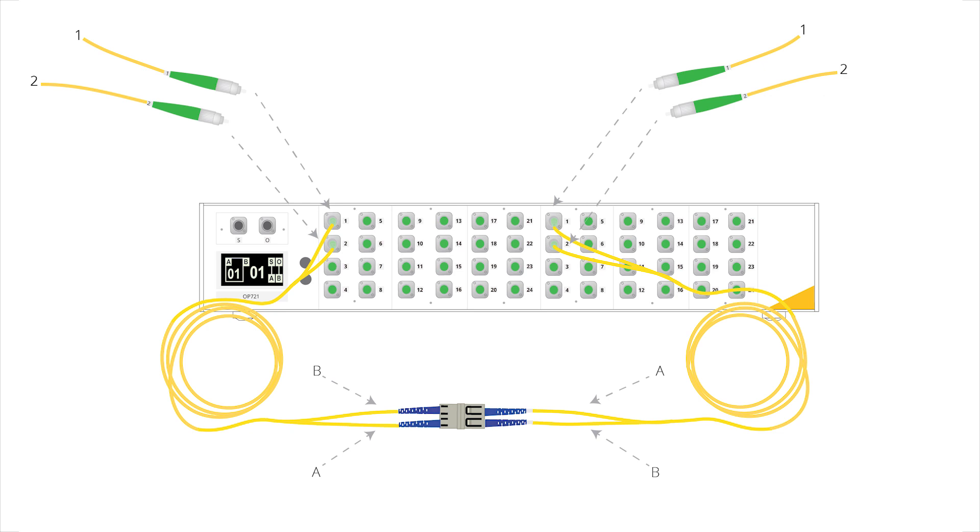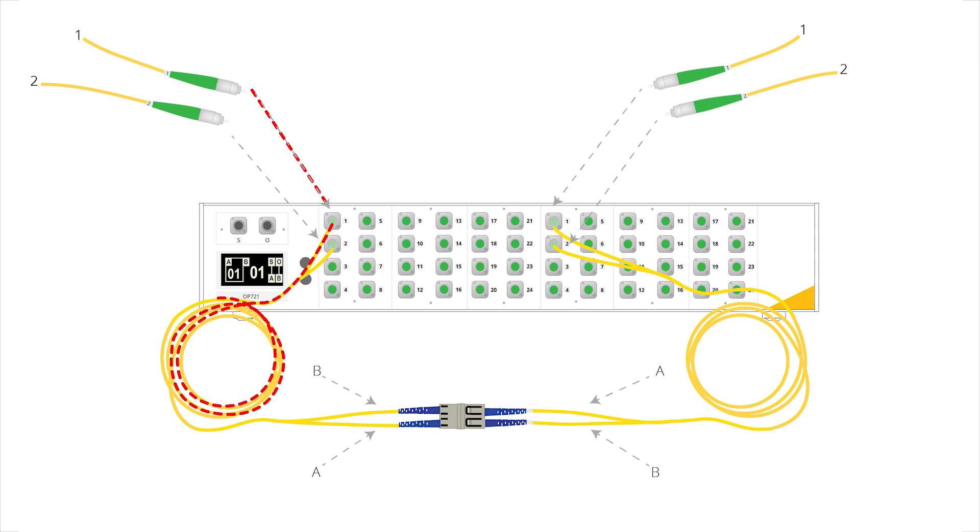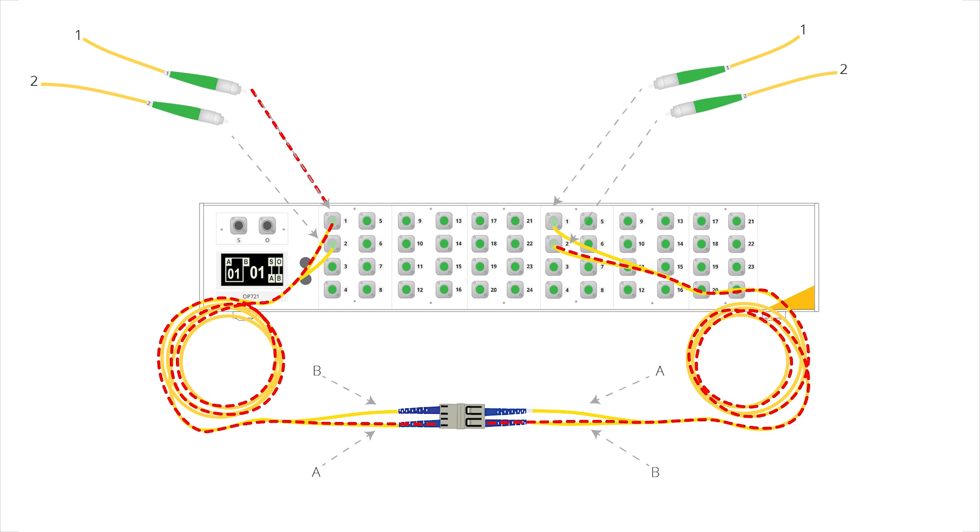Connecting to the OP721 in accordance with these labels creates a problem. Light will emit from the channel 1 port of the OP721 and enter fiber 1 of the first reference cable. But then, it passes into fiber 2 of the second cable. As a result, channel 2 on the other side of the OP721 receives the light, instead of channel 1, and the insertion loss reference for channel 1 comes up dark.